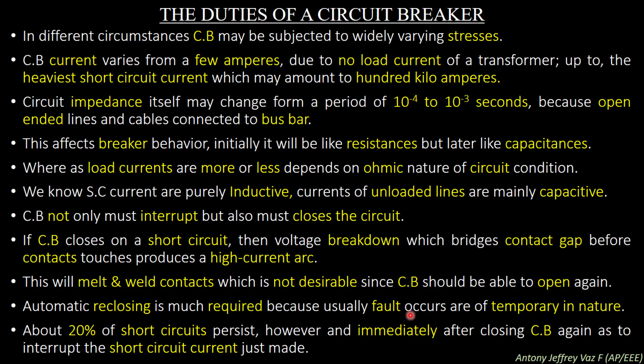About 20% of short circuits persist, however, and immediately after closing, the circuit breaker again has to interrupt the short circuit current just made. So out of 100% of short circuit faults, only 20% will persist in the power system. Others are temporary in nature. They will be okay after a few seconds or a few minutes. So automatic reclosing of the circuit breaker is very much needed so that human intervention is minimized.